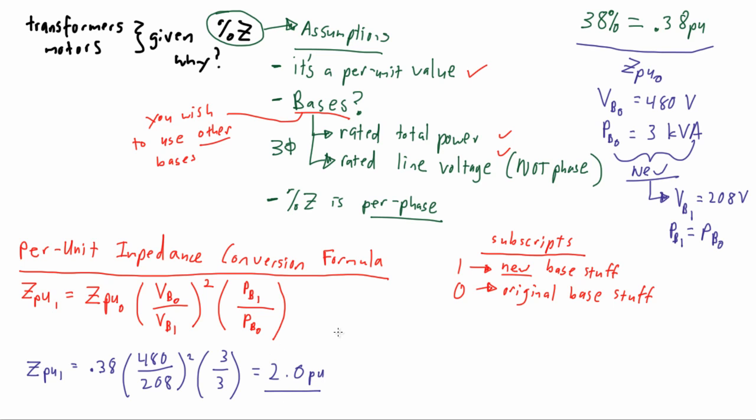So to analyze this formula simply, we've just filled in our variables. We have a 0.38 impedance per unit there. We have our 480 volts, which is our original voltage base, put over 208 volts, which is our new voltage base. We square that, and then we are not changing our power bases, so we can put the new over the original being the same. 3 over 3 obviously equals 1, which algebraically makes that whole parenthesis go away. And we can net out to a 2.0 pu.